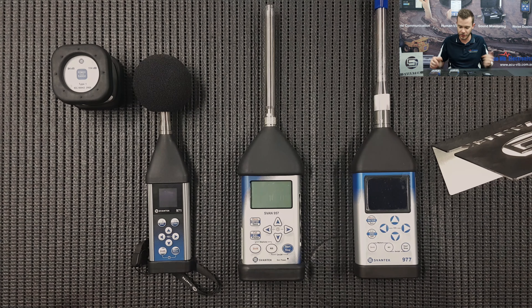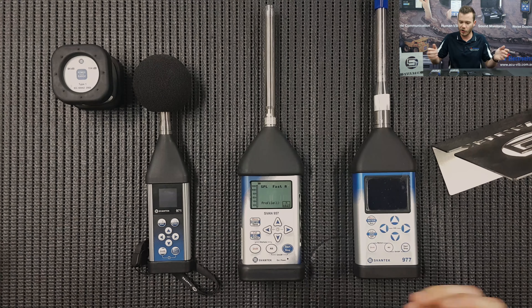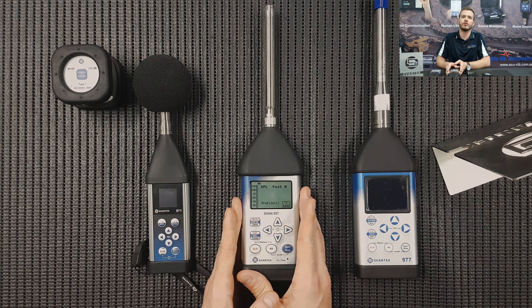So let's start. As you guys all know, on-off button — Alt and Start to turn it on. It's going to run through its setup menu. So let's just wait a few moments. There's a 60-second countdown warm-up timer, usually for colder climates. I'm just going to skip that. In Australia we should be fine.